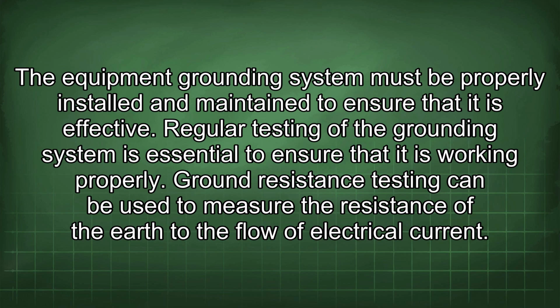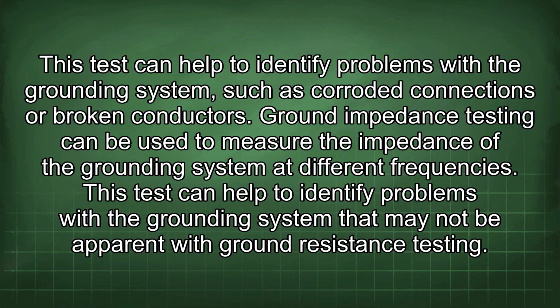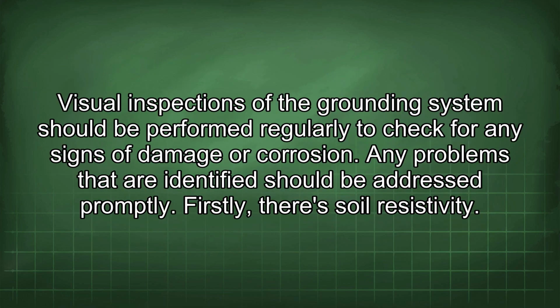Ground resistance testing can be used to measure the resistance of the earth to the flow of electrical current. This test can help to identify problems with the grounding system, such as corroded connections or broken conductors. Ground impedance testing can be used to measure the impedance of the grounding system at different frequencies. This test can help to identify problems with the grounding system that may not be apparent with ground resistance testing. Visual inspections of the grounding system should be performed regularly to check for any signs of damage or corrosion. Any problems that are identified should be addressed promptly.